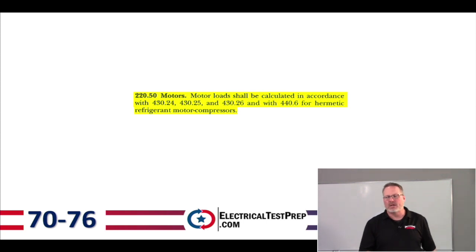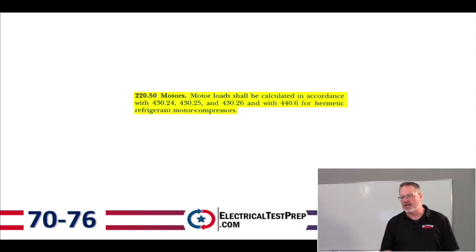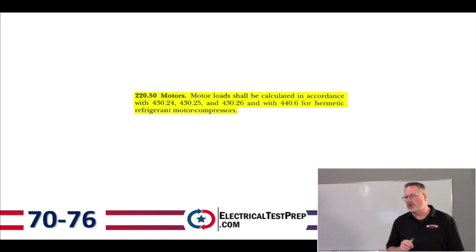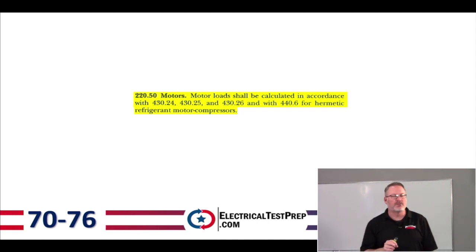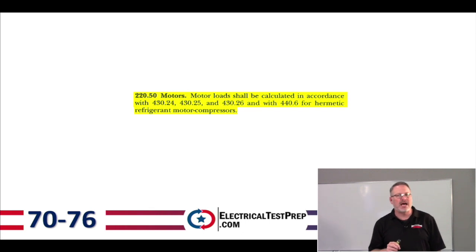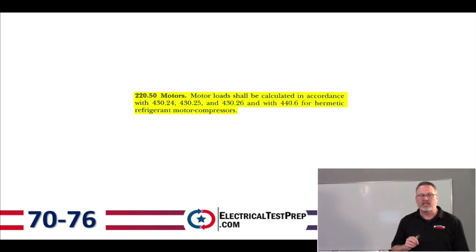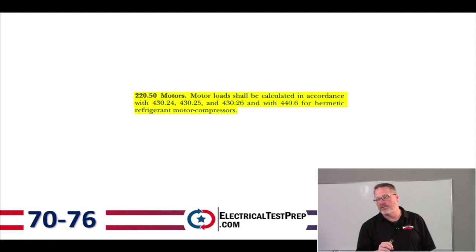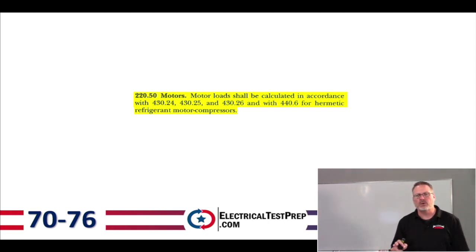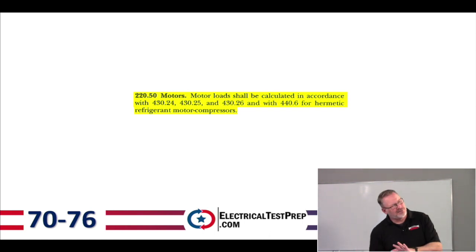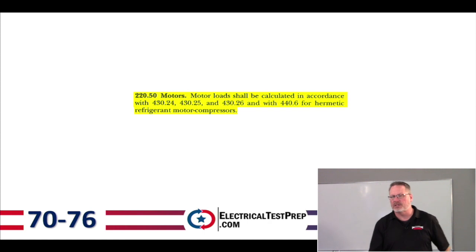Section 220.50, Motors — also on page 76. Motor load shall be calculated in accordance with 430.24, 430.25, and 430.26, and with 440.6 for hermetic refrigerant motor compressors. So to get the volt-amps for motors, we find that information in the motors chapter and then bring it into our calculation.